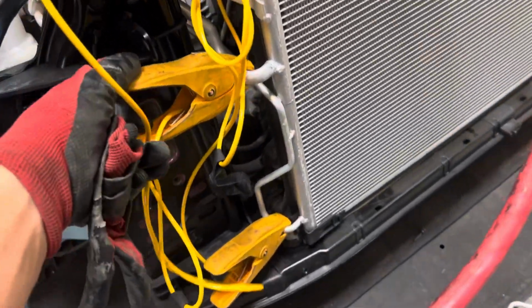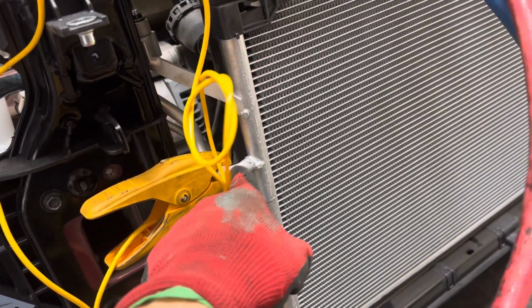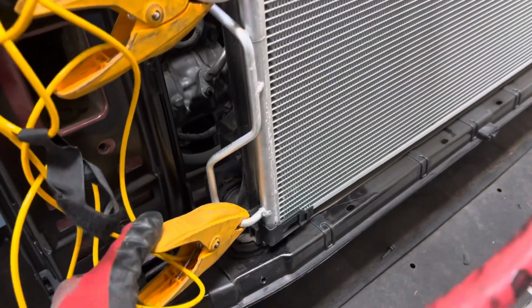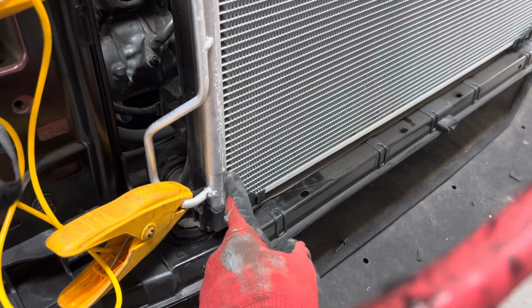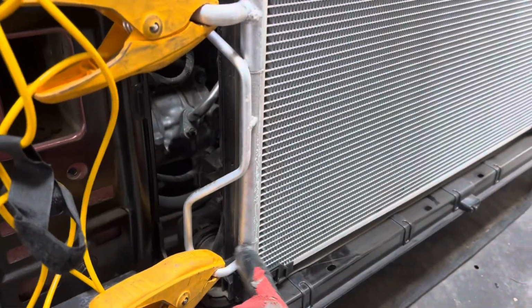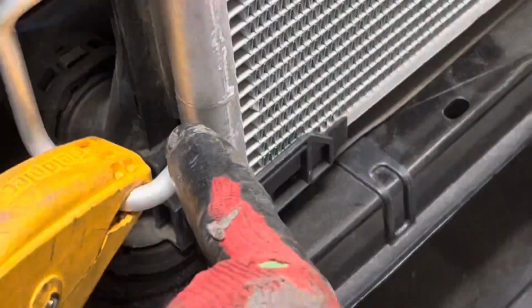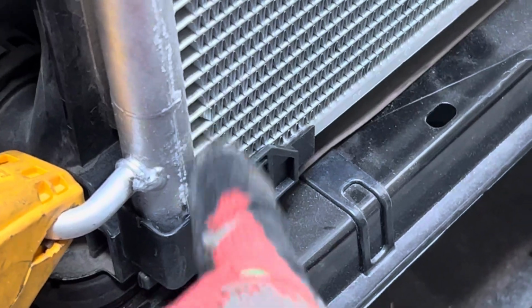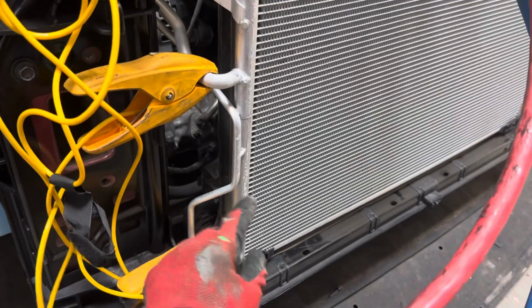So I have one temperature probe connected to the inlet, so that'd be hot vapor coming from the compressor going in. Then I have the other one on the outlet coming out. That's on the subcooling circuit, because these last few lines is subcooling liquid. Everything else up here is gas. Everything below this little line you see right here, that is subcooling. Everything here, subcooling liquid. Everything up above, gas. Minute amount of liquid as you get down in there.